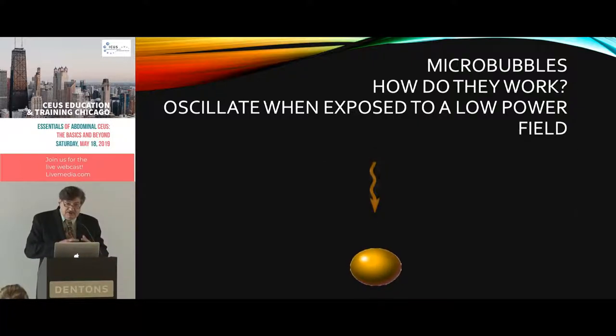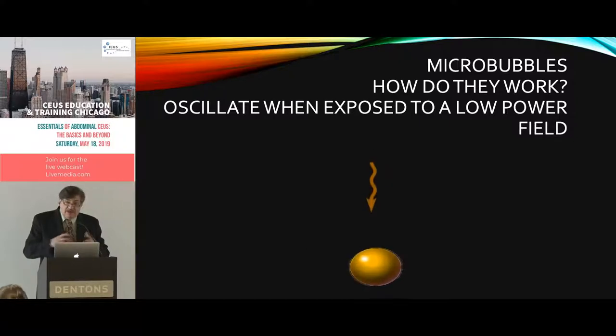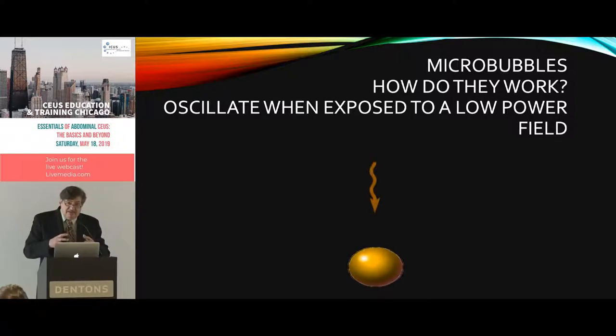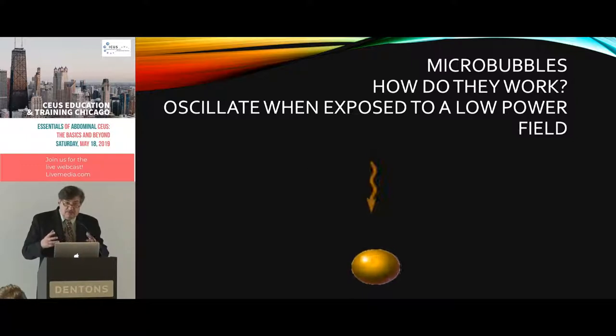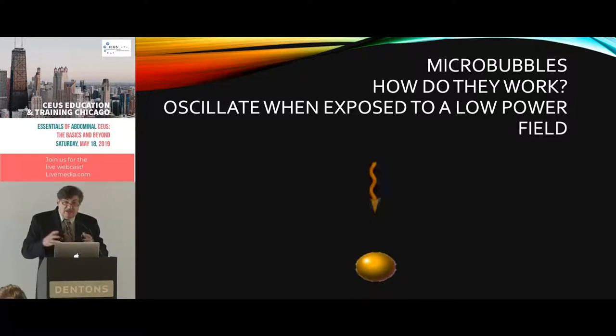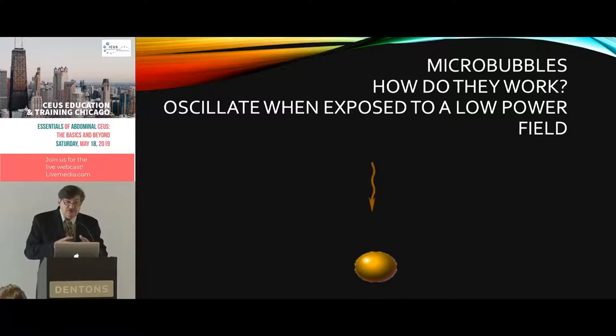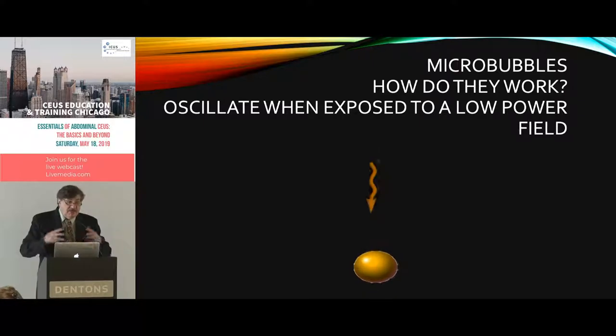We can have bubbles in a low-MI nonlinear response mode — still considered low MI — where we use that nonlinear response to get a contrast-only image. If we use very high MIs, we just bust the bubbles and they're gone. To image these agents we need contrast-specific software, and this software operates at the low MI in the region where we're getting the nonlinear response.